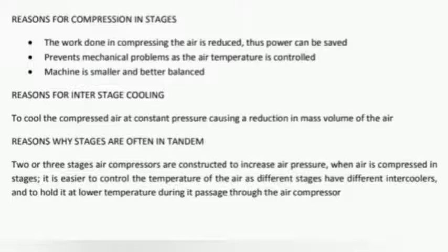To cool the compressed air at constant pressure, causing a reduction in the volume of the air. Number 2. Reduction in temperature makes lubrication of the later stage liners possible and also adds to the safety of the system. Another importance of interstage cooling is that moisture in the air and perhaps oil vapor may condense and can be got rid of with the help of the drains.